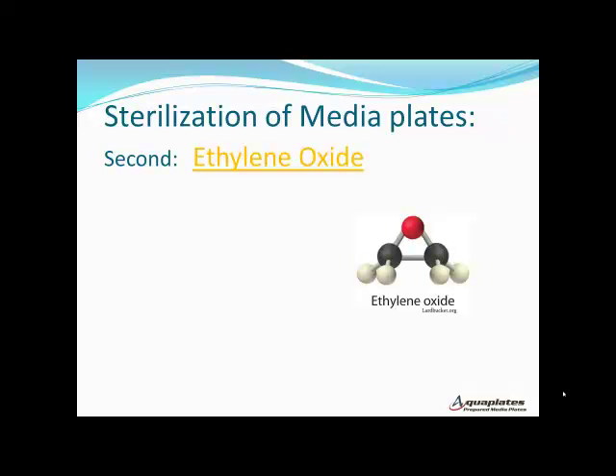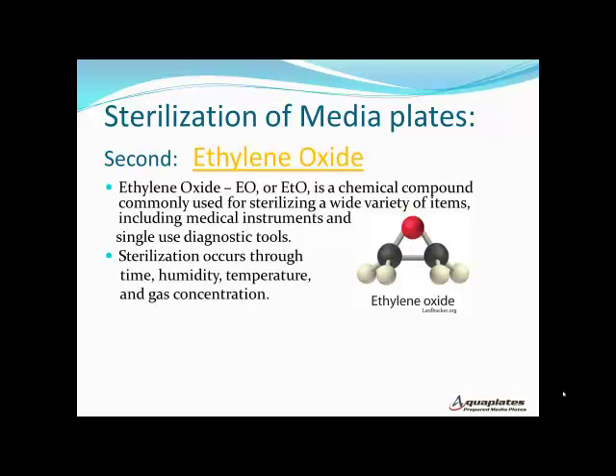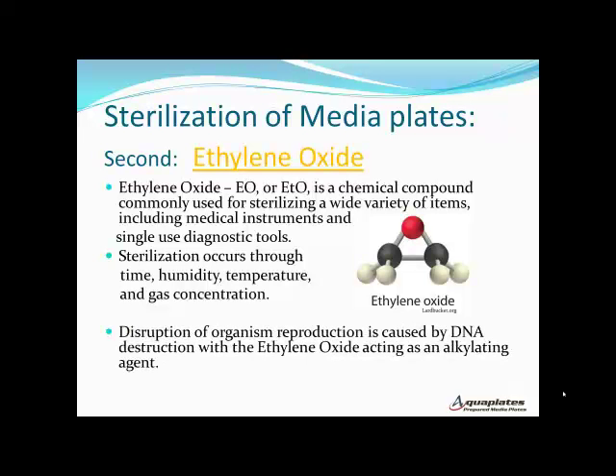Sterilization of media plates — second on the list — ethylene oxide. Ethylene oxide is a chemical compound commonly used for sterilizing a wide variety of items, including medical instruments and single-use diagnostic tools, like scalpels. Sterilization occurs through time, humidity, temperature, and the concentration of ethylene oxide. Disruption of organism reproduction is caused by deoxyribonucleic acid destruction, with the ethylene oxide acting as an alkylating agent.